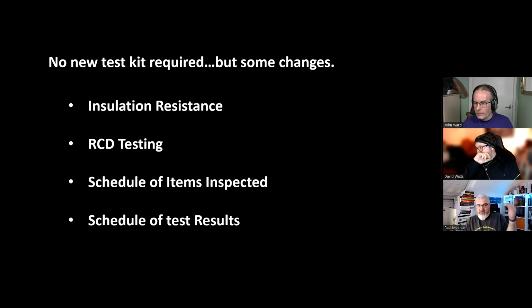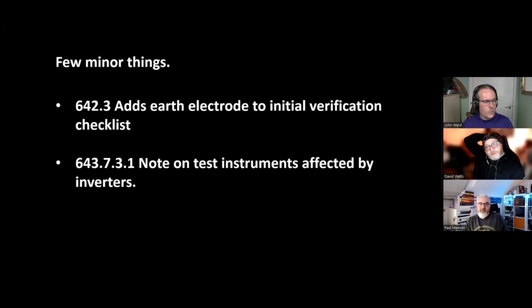Basically, in summary: IR, RCD testing, schedule of items inspected, and schedule of test results. We'll go into it now, but before we do, there's a couple of minor things. The initial verification checklist has added the earth electrode requirement earlier on, and it also has a weird note in 643731 about doing tests and test instruments being affected by inverters.